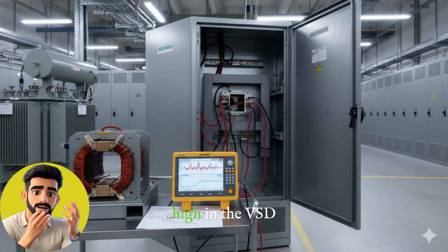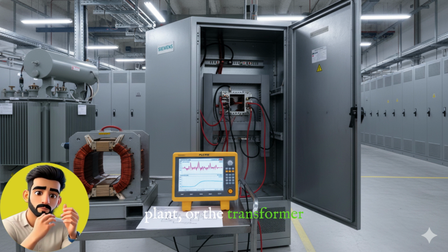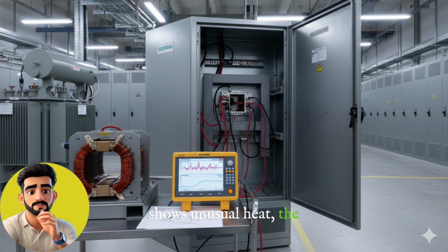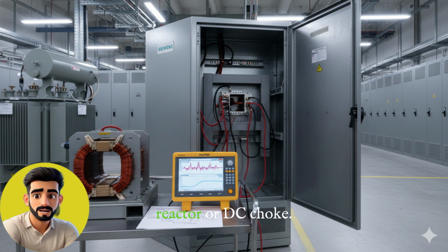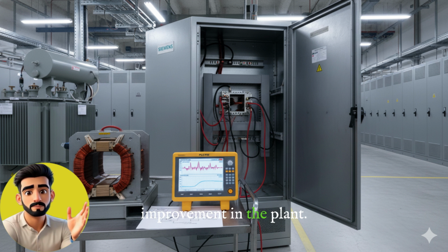If the harmonics are high in the VSD plant or the transformer shows unusual heat, the very first step is to install a line reactor or DC choke. This is a simple device, but it provides a very significant stability improvement in the plant.